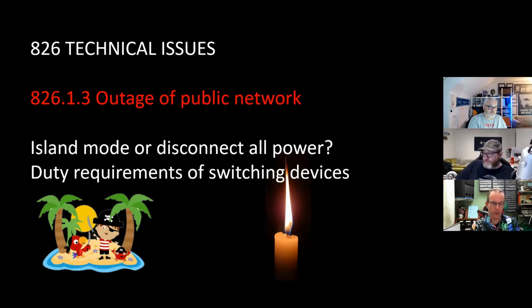Then we've got duty requirements for switching devices, which was mentioned earlier in the comments. Yes, it is going to put loads of strain on switching devices. A lot of these devices out there now are designed for temporary or standby use, and might only be used, say, once a year, which is when they decide to test the generator in the basement and switch over to that.